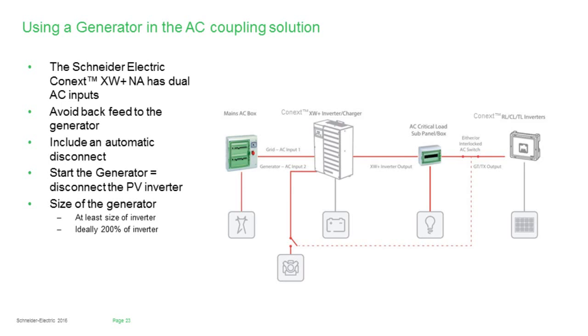because of the risks that are involved. So what we suggest doing, and this is within the AC coupling white paper that Schneider Electric has, is that we actually have a disconnect switch so that when the generator's running, we're actually disconnecting that PV inverter. And once the generator is switched off, then we reconnect the PV inverter. So it's an or statement. Either the generator is connected to the charging source as the charging source for the batteries, or the PV inverter is. You can't have both. There are some special applications, but we won't get into that.